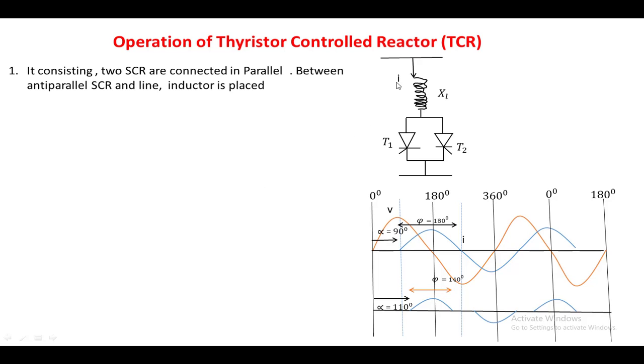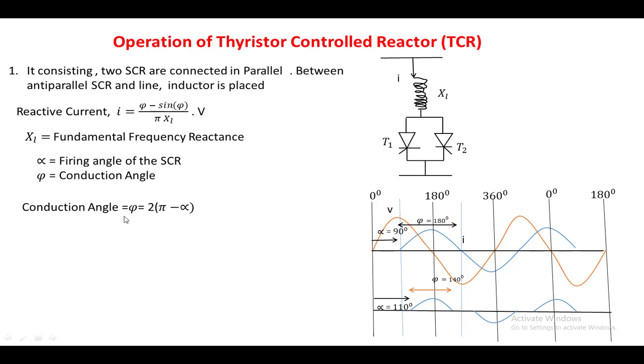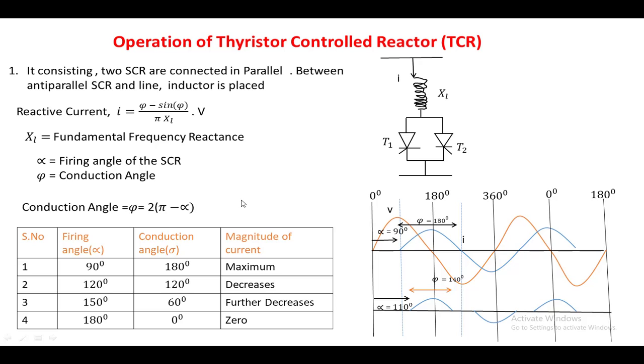The expression for the fundamental current is: I = (psi − sin(psi)) / (π · XL) · V, where psi is the conduction angle, XL is the inductive reactance, and V is the applied voltage. As shown in the table, as the firing angle increases the conduction angle decreases, and the current magnitude decreases from maximum to zero. By changing the firing angle between 90 and 180 degrees, the reactive current magnitude can be varied continuously.